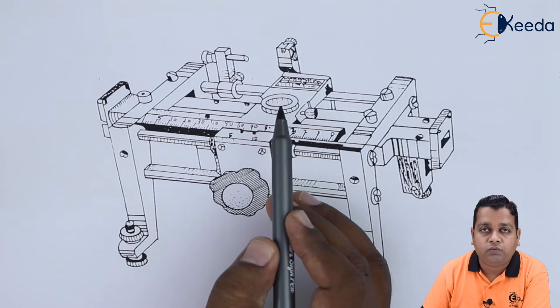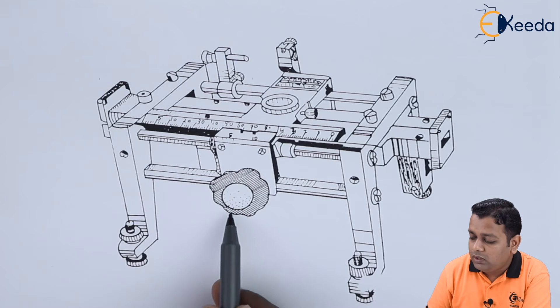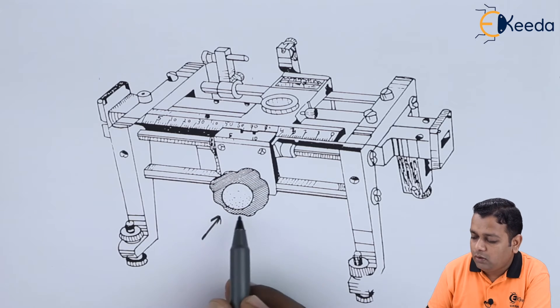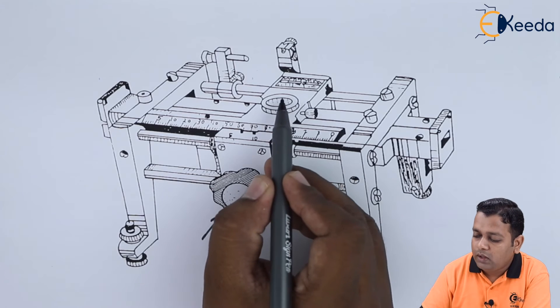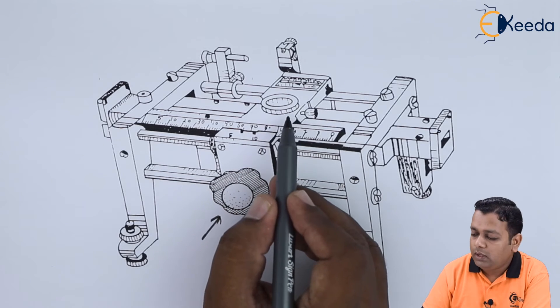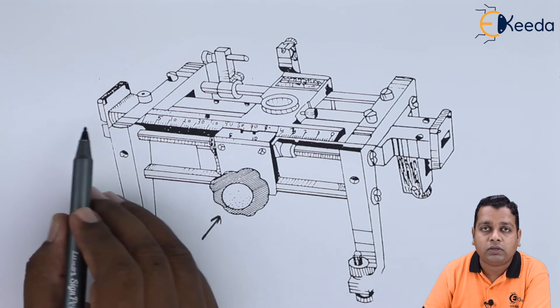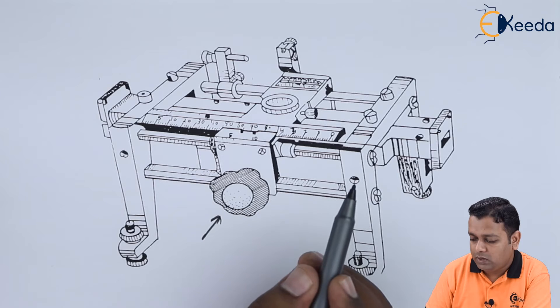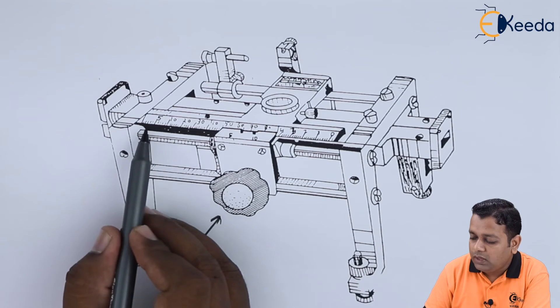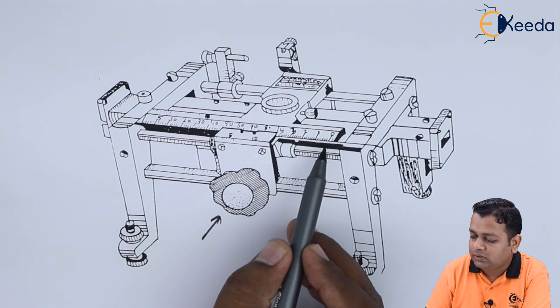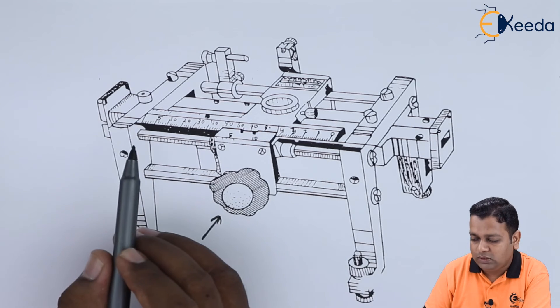We can have the mounting, and with the help of this particular knob we can have the position of this mounted coupling probe changed from one end to another end throughout the entire length of the rectangular waveguide. Now to measure the position, we have scale markings at different values throughout this linear dimension.